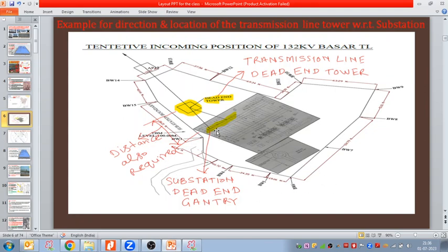So when we make the layout drawing, we should also know the tentative information about where the dead end tower locations are coming. This is what I mean by dead end tower and dead end gantry. The last tower of the overhead transmission line, I call the dead end tower — transmission line finishes there and the substation begins. The last tower of my substation, I call the substation dead end tower, which I will show you in this drawing.